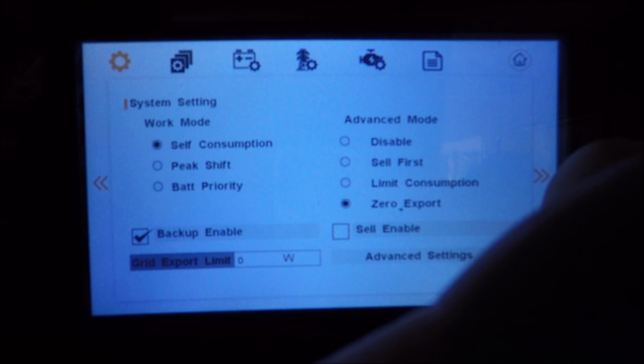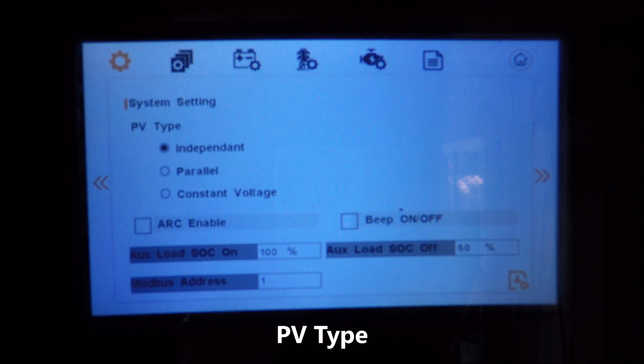I'm going to go to the next page, and that's going to be PV type. For most use cases, the PV type will be set to independent. This allows the inverter to manage the 4 MPPT charge controllers independently. So, for instance, if one array is producing 1,000 watts and another array is producing 500 watts, you'll get 1,500 watts. This can happen, for instance, if there is shading on one array but not shading on another, or if you have an array mounted on one side of the peak of your house and another array mounted on the other. Normally, you would have to use some external device to manage the differences in voltage because the arrays would either be shaded or receiving different amounts of sunlight. That is what makes the independent PV type very useful in setup.